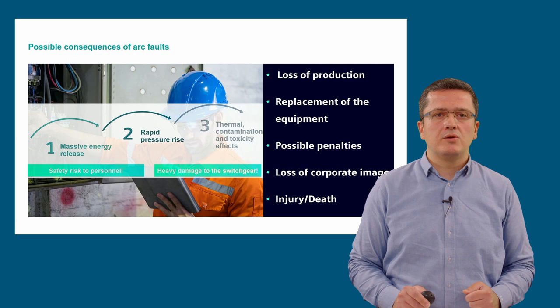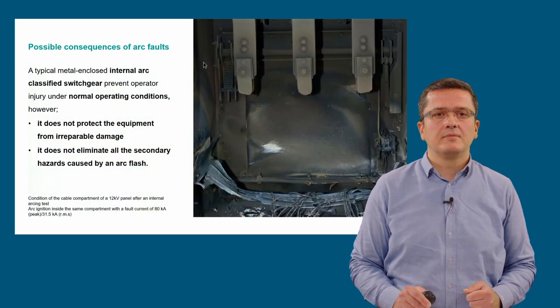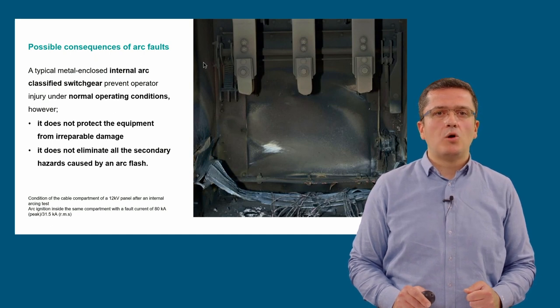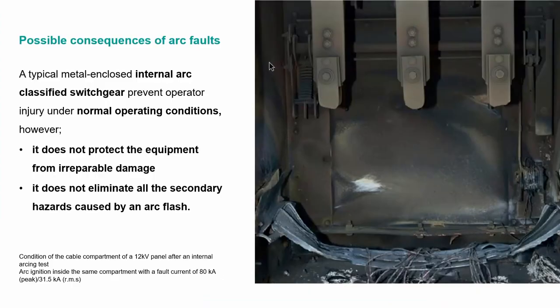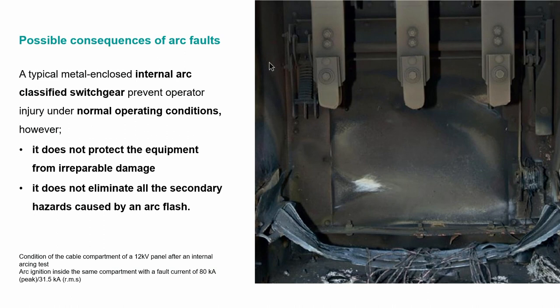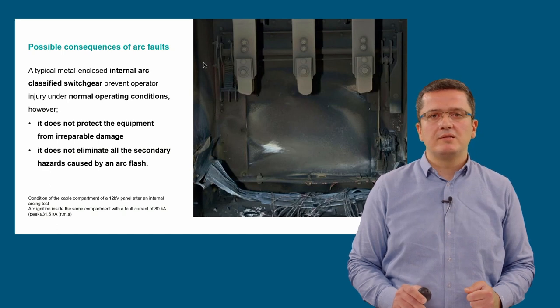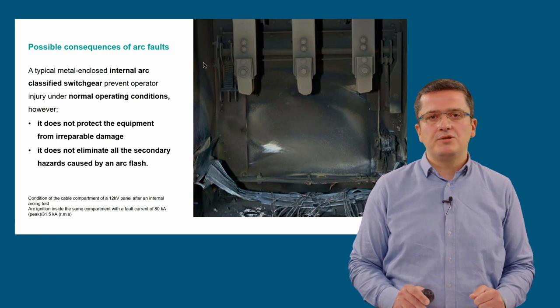Accordingly, possible consequences on the equipment, processes, and human beings are various. An internal arc classified switchgear can prevent operator injury under normal operating conditions, which is the status where all doors and covers are closed as per IAC. But it does not protect the equipment from damage and does not prevent the occurrence of secondary hazards like pressure wave, sound blast, blinding light, fire, toxicity, contamination, etc.